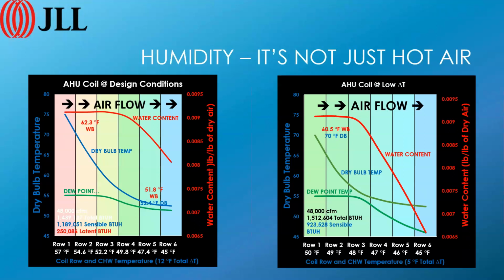Well, if you look at row number 3, the water temperature is 48 degrees. On the other coil, 48 degrees occurred in the 5th row. Now it's in the 3rd row. Well, that's when water is going to start coming out of the coil at 48 degrees because of the condition of the air. So the dry bulb temperature is still 52 degrees as a dry bulb control, but because the coil is so much colder as a whole, it's going to start to dehumidify more, and you're going to start to pull more moisture out of the air.